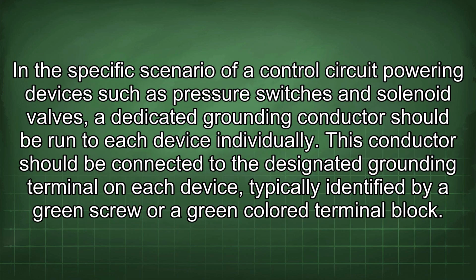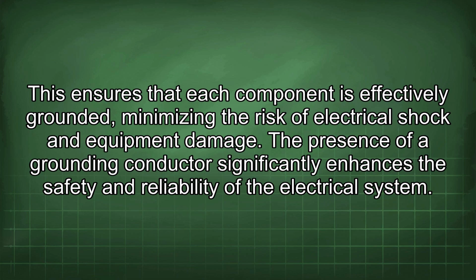In the specific scenario of a control circuit powering devices such as pressure switches and solenoid valves, a dedicated grounding conductor should be run to each device individually. This conductor should be connected to the designated grounding terminal on each device, typically identified by a green screw or a green-colored terminal block. This ensures that each component is effectively grounded, minimizing the risk of electrical shock and equipment damage. The presence of a grounding conductor significantly enhances the safety and reliability of the electrical system.